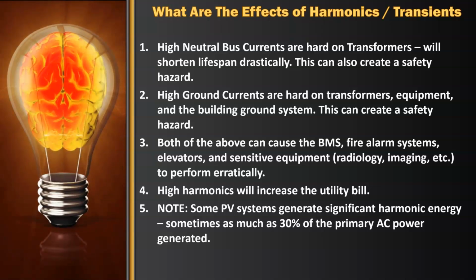And now the point number 5, love point number 5. PV systems generate, some of them generate a significant amount of harmonic energy. It's not unusual for a 1 meg PV system that has sort of middle of the road inverters on them to generate as much as 200 kilowatts, or maybe even as much as 300 kilowatts of harmonic energy.